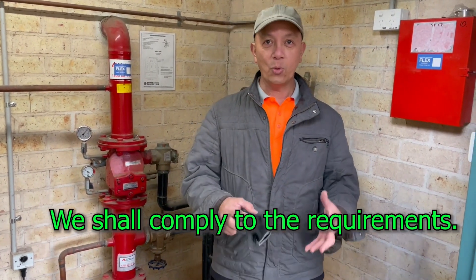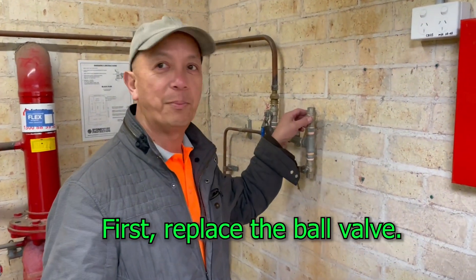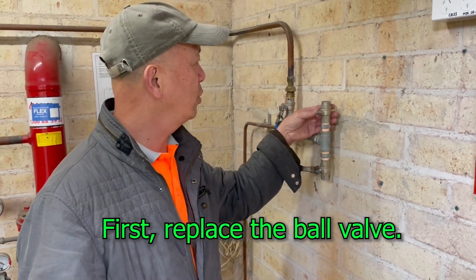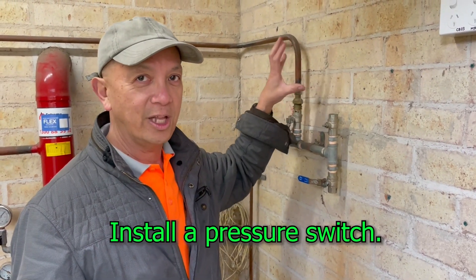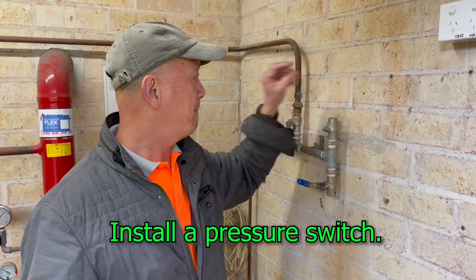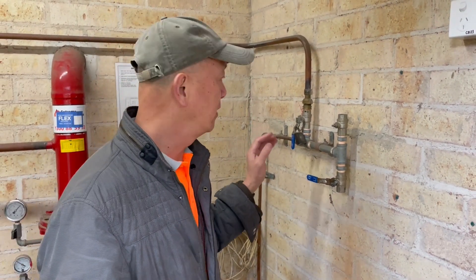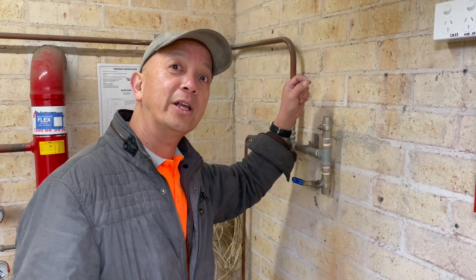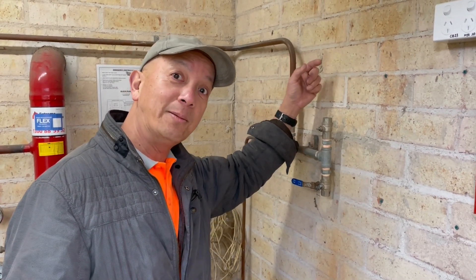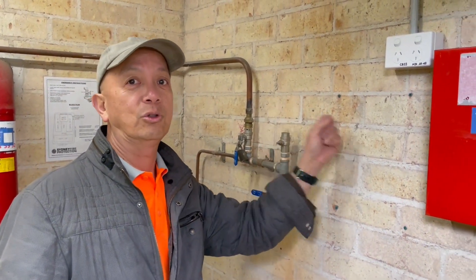Now we want everything to be compliant. What will happen today is we're going to replace the ball valve and install a new one and a pressure switch. That pressure switch will monitor any sprinkler activation — water goes up to the pressure switch, and it's connected to a normally open contact that becomes closed on an activation and triggers an alarm to the ASE.